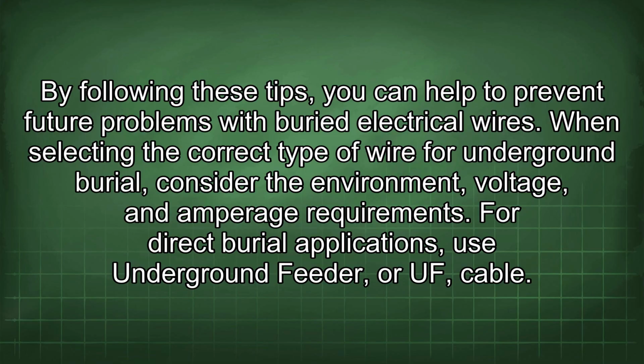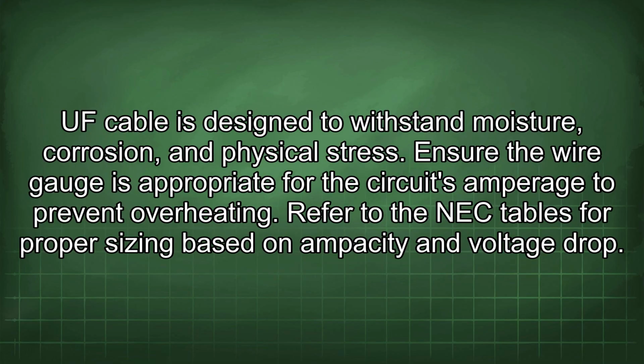When selecting the correct type of wire for underground burial, consider the environment, voltage, and amperage requirement. For direct burial applications, use underground feeder or UF cable. UF cable is designed to withstand moisture, corrosion, and physical stress. Ensure the wire gauge is appropriate for the circuit's amperage to prevent overheating. Refer to the NEC tables for proper sizing based on ampacity and voltage drop.